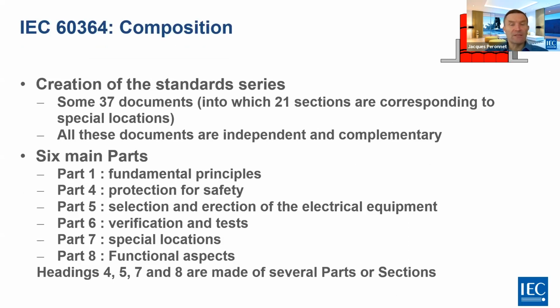The composition of IEC 60364 is a series of standards. That means that we have some 37 documents, of which 21 correspond to special locations. All these documents are independent and complementary. We have 6 main parts. Part 1 is the fundamental principles, part 4 is protection for safety, part 5 is selection and erection of electrical equipment, part 6 is verification and test, part 7 is special locations, and part 8 is functionalities. Parts 4, 5, 7, and 8 are headings, which are made of several parts and sections.